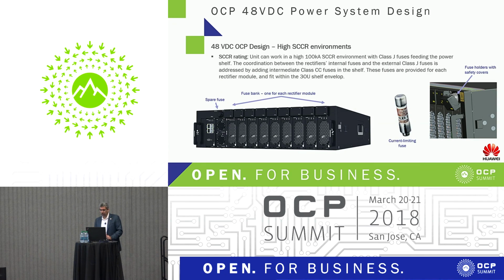In order to deal with short circuit current rating, we also added fuses on the shelf. Again, this is to help reduce all those other pieces of equipment in the data center. So we have current limiting fuses in the shelf to help maintain a high SCCR rating for the shelf. This is important so it can survive in these more optimized environments.